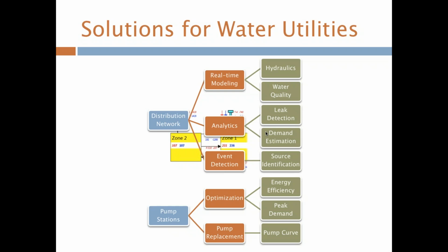So once you have that, then it's simple arithmetic to know how much water is being consumed, both the non-revenue water as well as the actual demand that's going into the system. And the way you use that information is if you actually can separate that kind of process into separate zones or in the entire system, then you can fine-tune the demands that you used when you did your planning model to reflect what's really happening in an operational sense in the system.